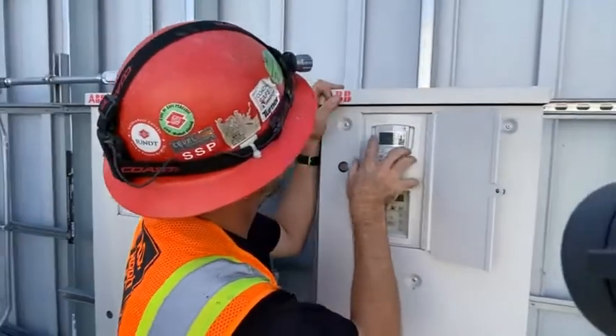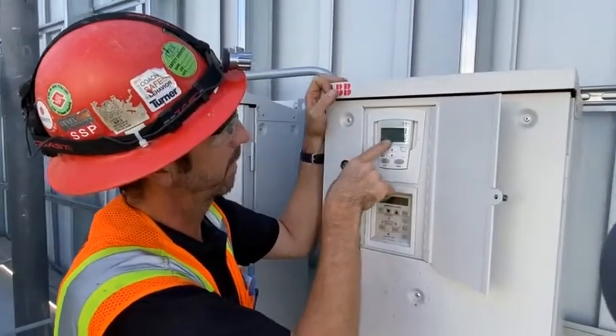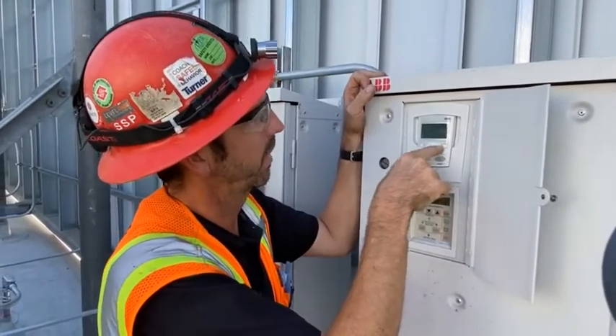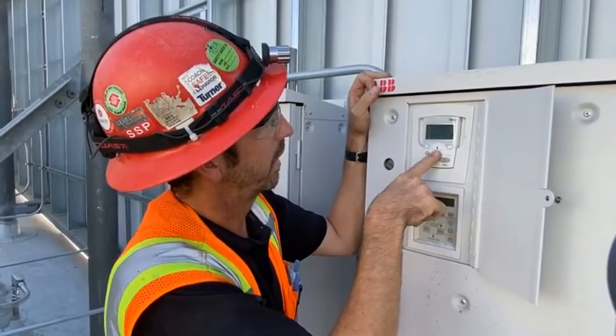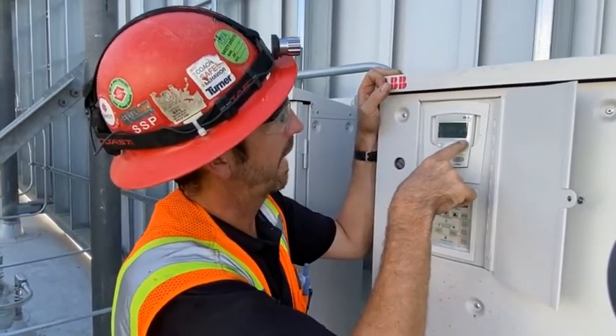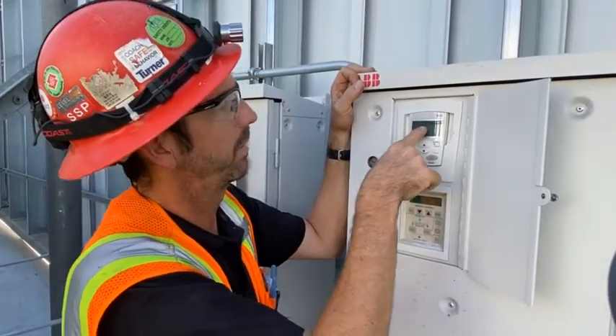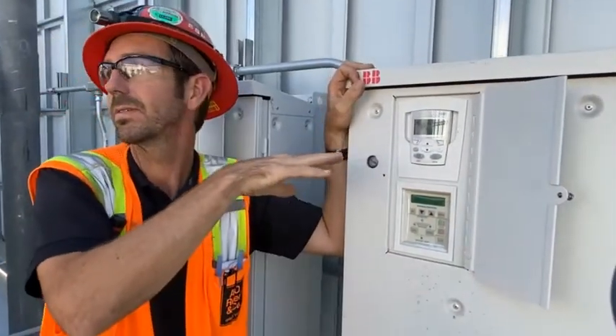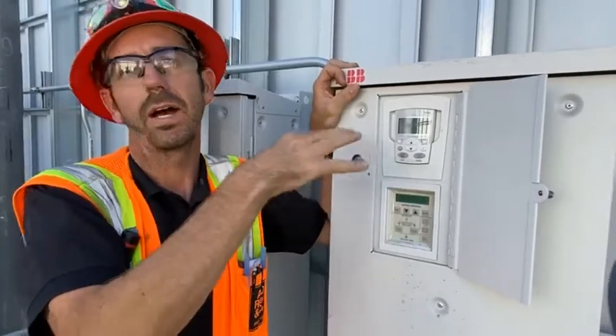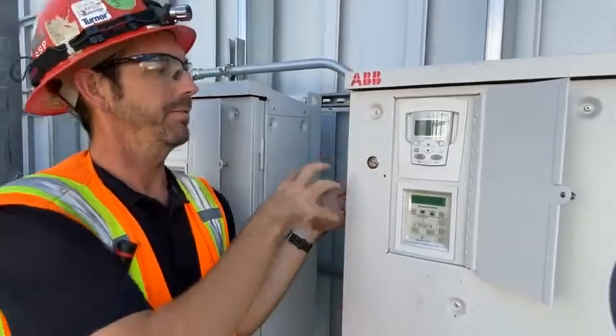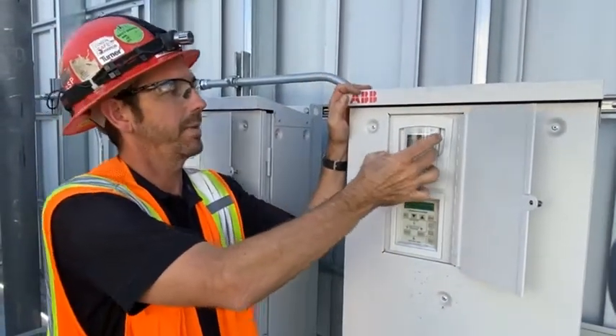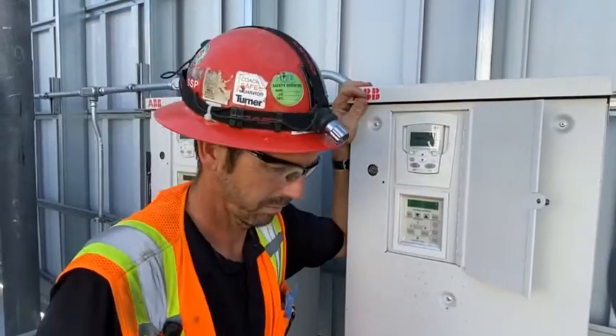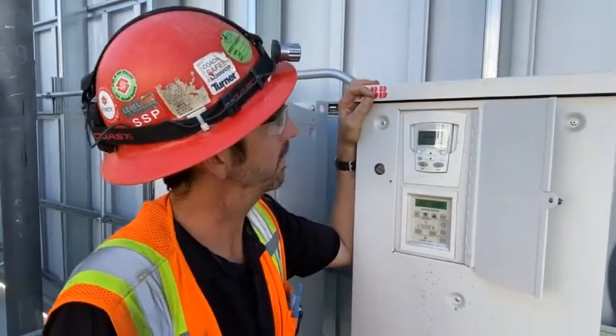So now we'll go back to the main menu, the main display. We press menu once. We go down to parameter backup. We go upload to panel. Are you guys familiar with this? When you make a change? So when I upload the parameters into the panel, I'm taking the information out of the drive, sucking it into the keypad, okay? It's copying.